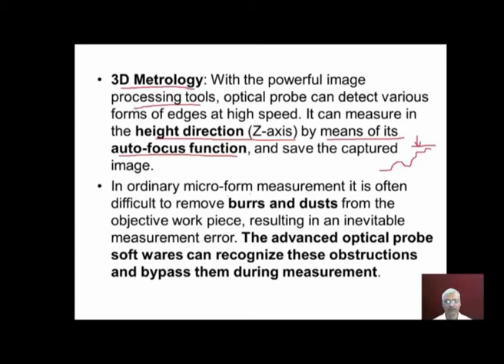In ordinary microform measurement, it is often difficult to remove burrs and dust. For example, we have a workpiece like this wherein there is a hole, and here some burrs are there. So in ordinary measurement, compensation for these burrs cannot be made. Whereas if we use vision type probes, these burrs and dust can be removed automatically. The advanced optical probe software can recognize these obstructions like burrs and dust and bypass them during the measurement.